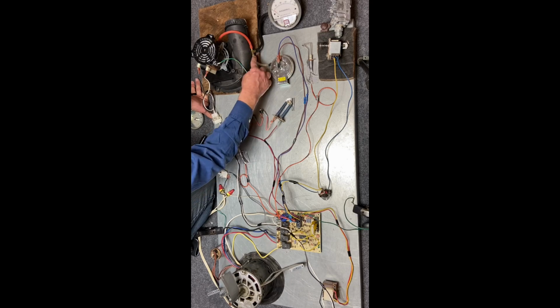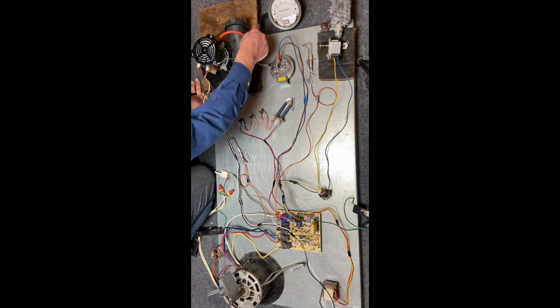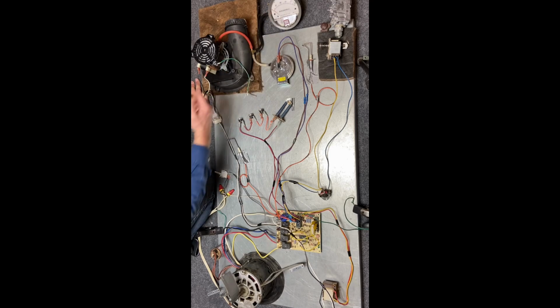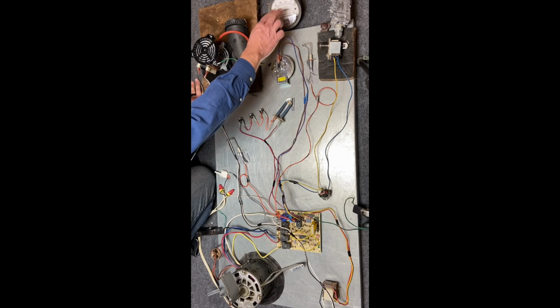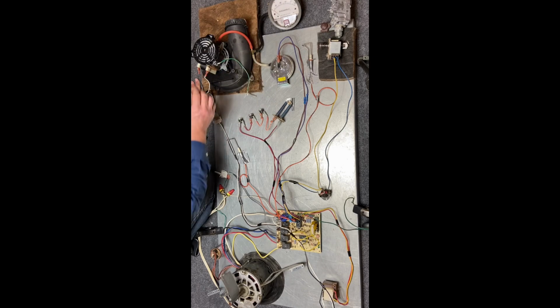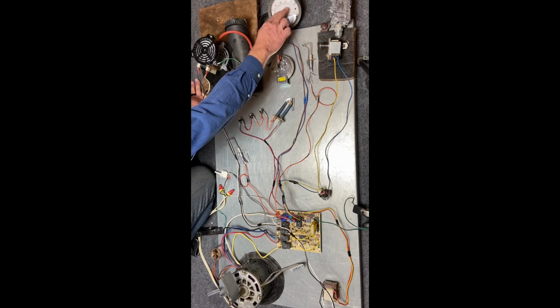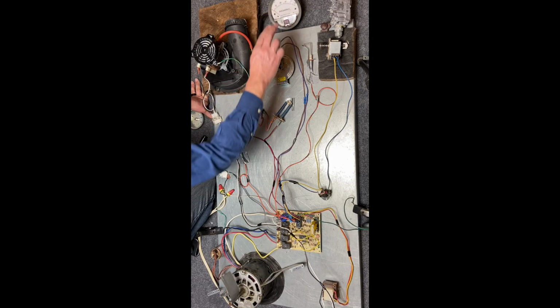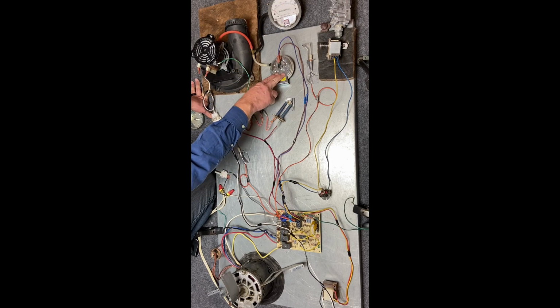So what I've done is added a T in here and added a component which is called a Magnehelic. There's digital versions of these, but it's still going to measure our vacuum. So when this motor is running, we're going to see how many inches of water column I have, to see if this switch is going to have enough vacuum to close. Now if I want to check this switch, I can put my meter in the 2 points. If I'm getting 24 volts, the switch is open. If I'm getting 0 volts, the switch is closed. So it's still, again, just 2 wires in.